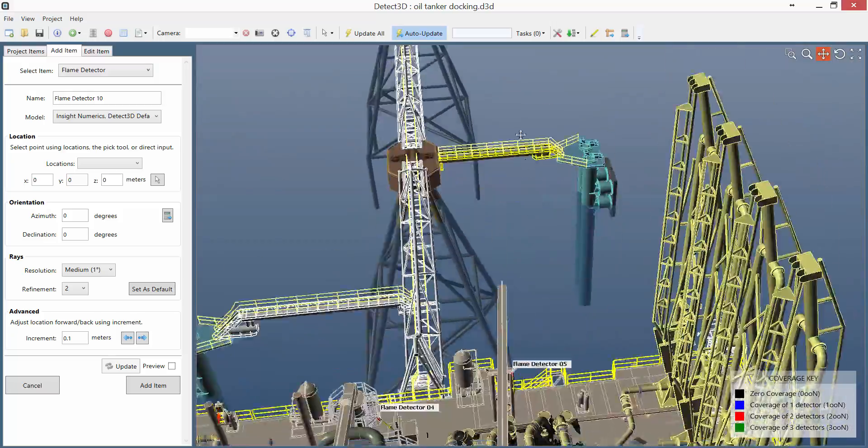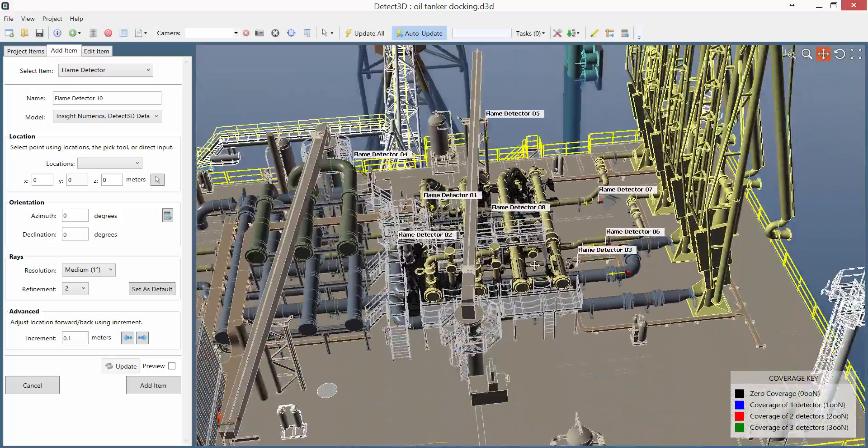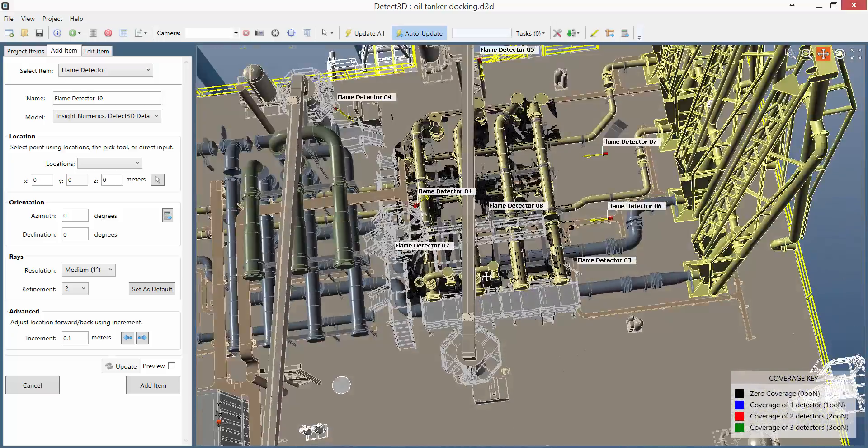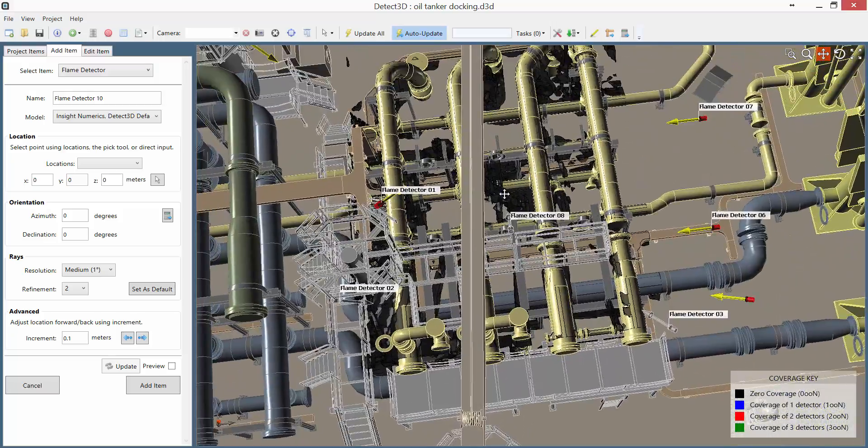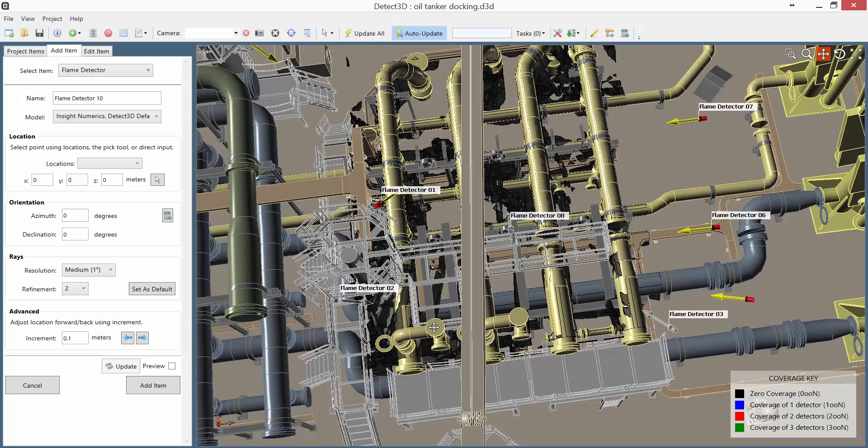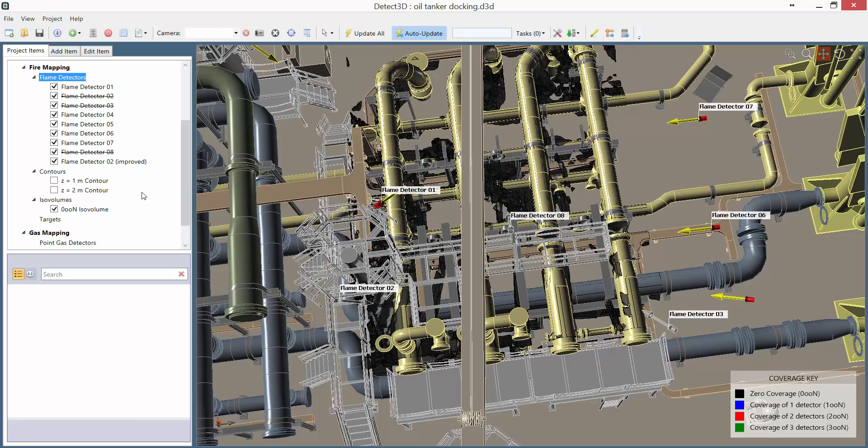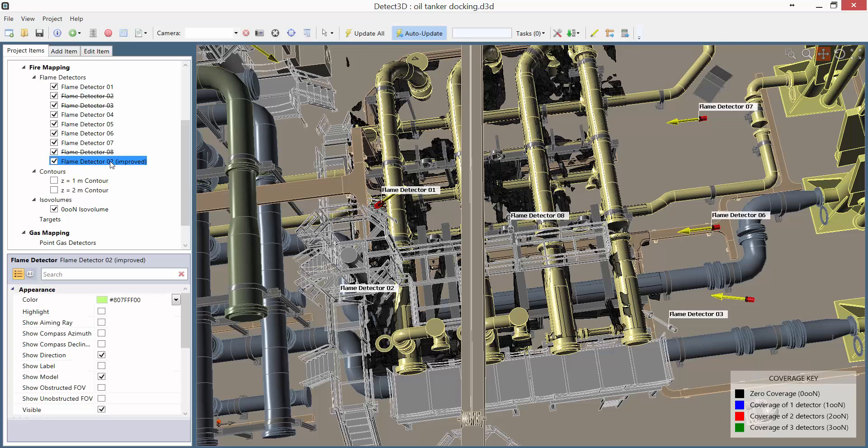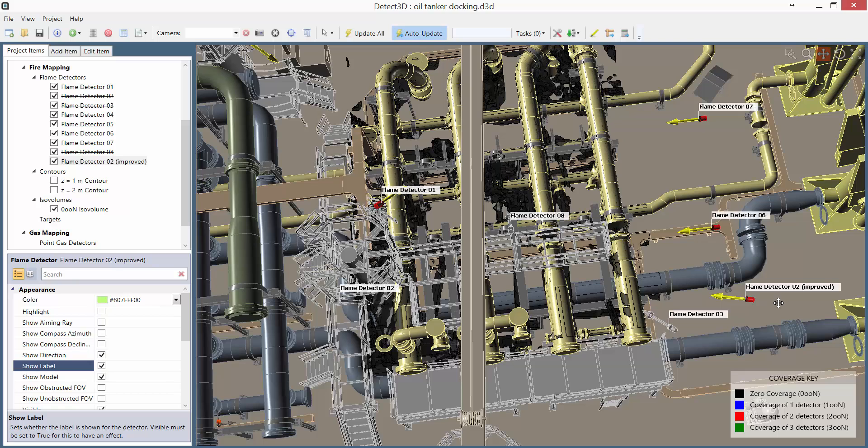I can now take a look at my updated zero coverage ISO volume, and I can see the blind spots have reduced pretty well. I'm pretty confident of getting above 90% coverage, and I can see my new detector, the improved detector 2, now positioned here.